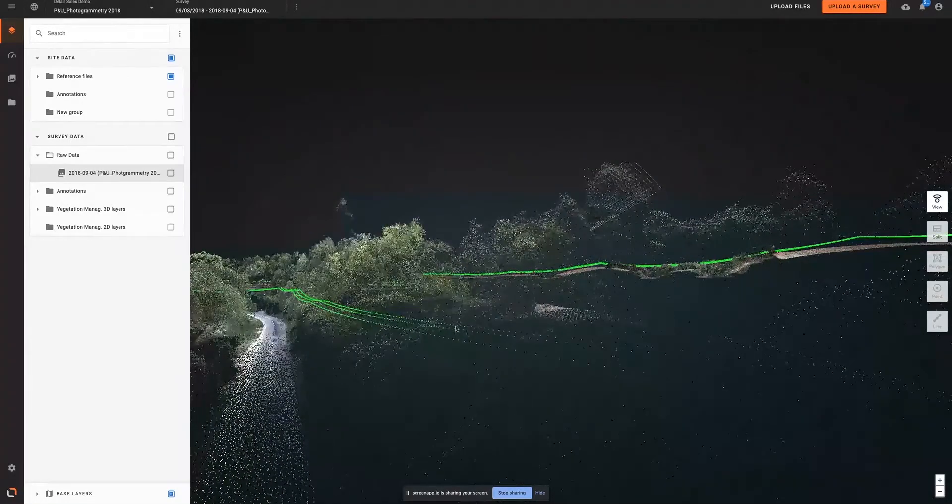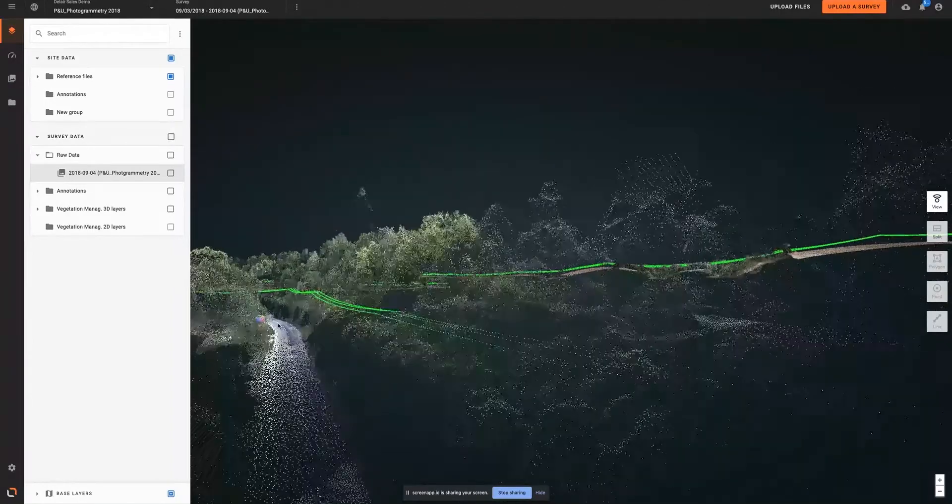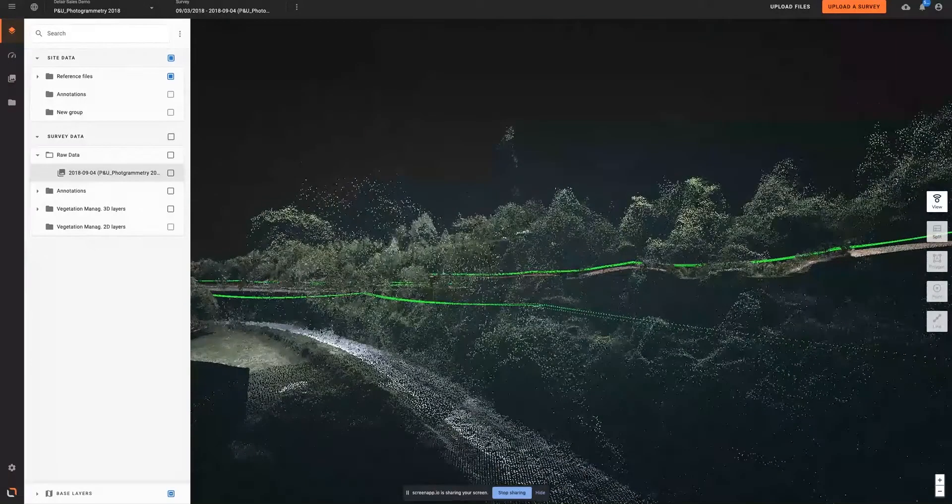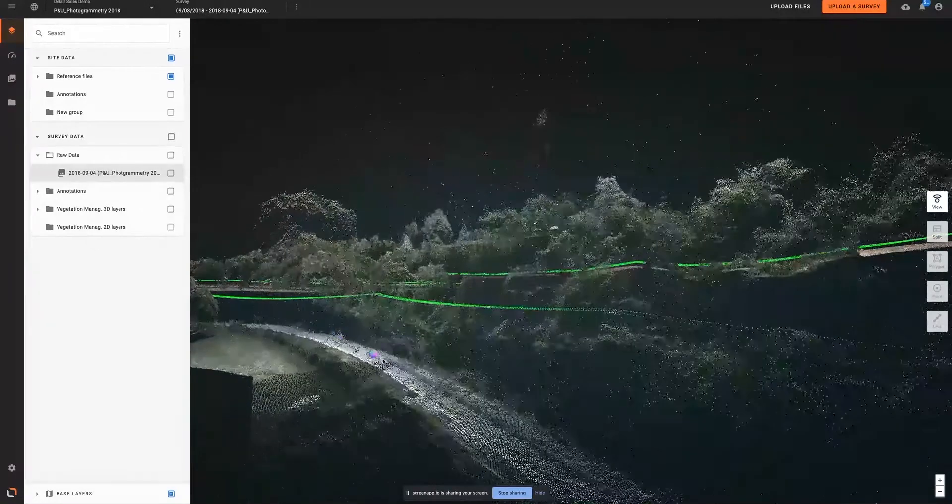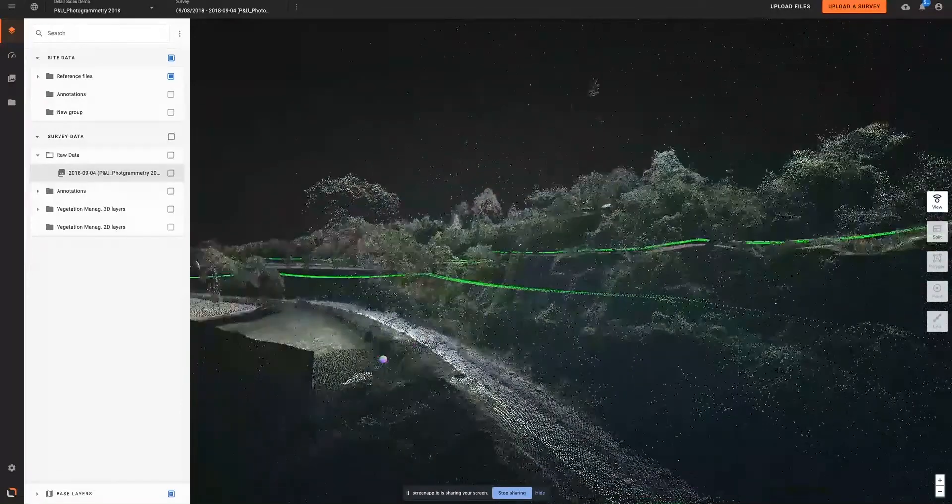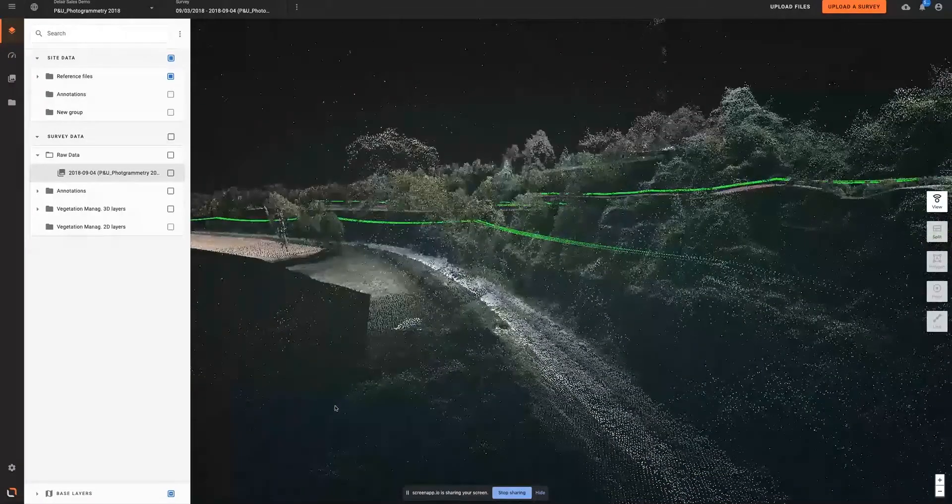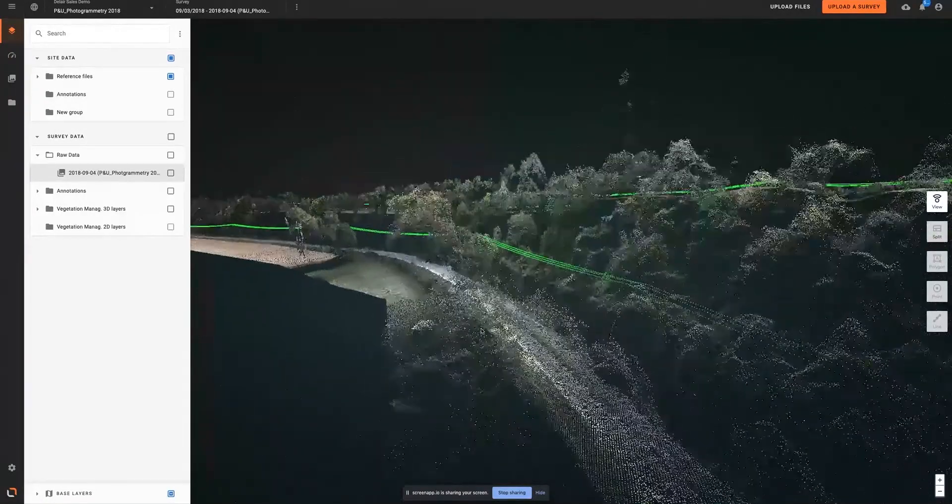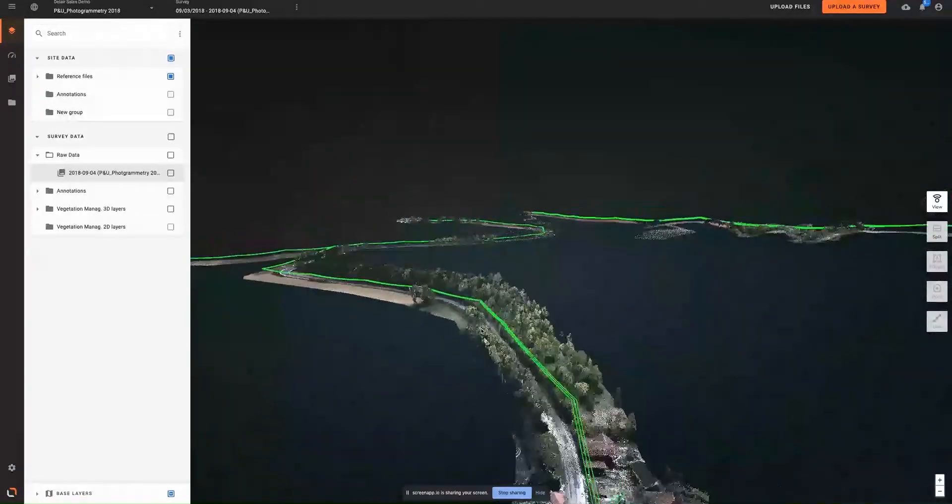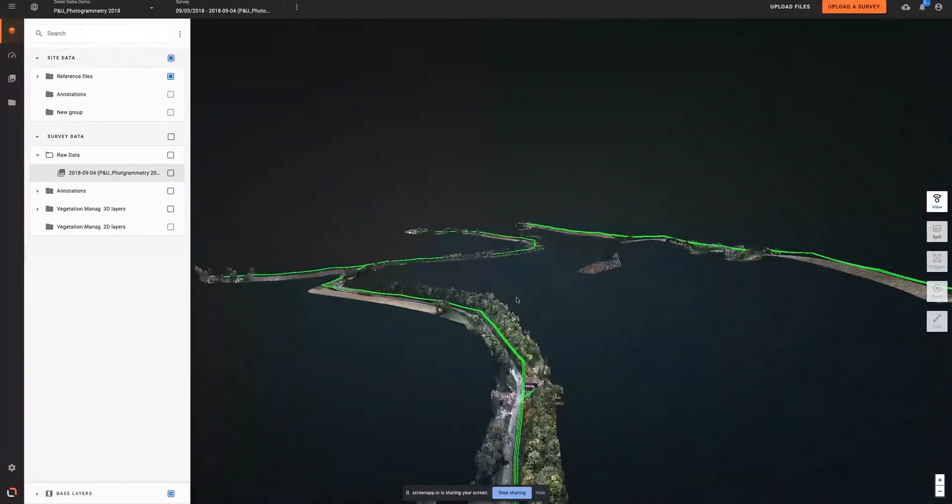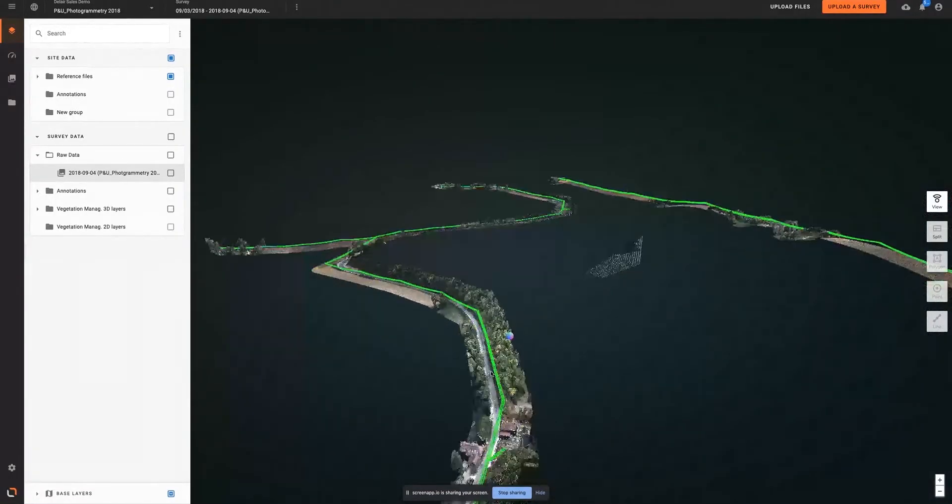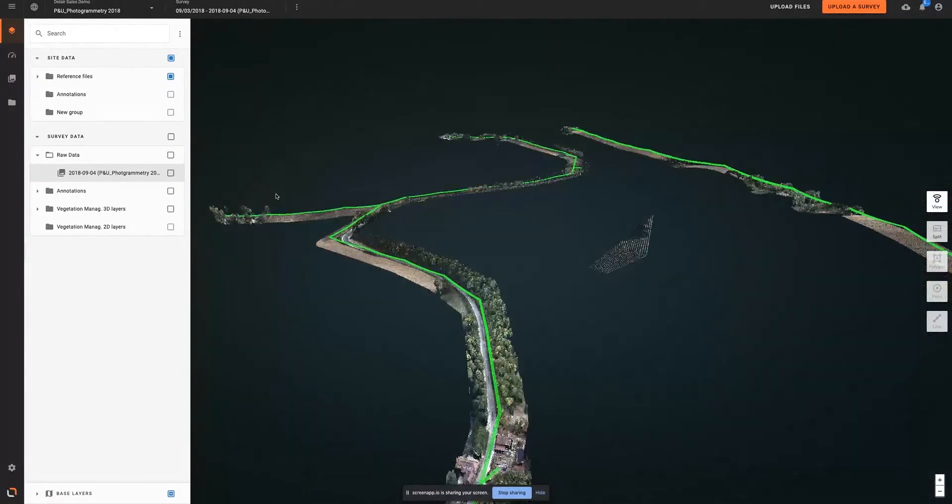For this vegetation management analysis, the AI takes all the vegetation points and calculates their distance and position from the powerline. The risk classes are distance and position based, but also incorporate additional line characteristics, such as transmission line voltage.